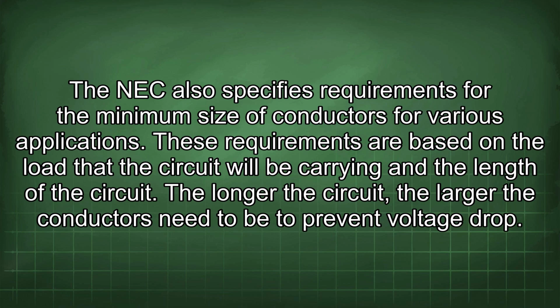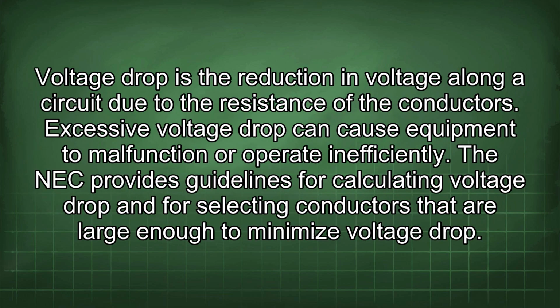The NEC also specifies requirements for the minimum size of conductors for various applications. These requirements are based on the load that the circuit will be carrying and the length of the circuit. The longer the circuit, the larger the conductors need to be to prevent voltage drop. Voltage drop is the reduction in voltage along a circuit due to the resistance of the conductors. Excessive voltage drop can cause equipment to malfunction or operate inefficiently. The NEC provides guidelines for calculating voltage drop and for selecting conductors that are large enough to minimize voltage drop.